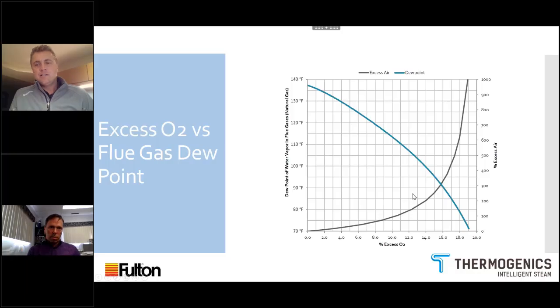So the number of hospitals we've been into, in particular brand new ones, that are designed around 130 degree F supply and 100 degree return, as you can see by this chart, if they're running anywhere above these O2 rates, you're not going to actually see condensing of that flue until you get down around 90 degrees. So it's important to understand the style of the appliance that you might be wanting to retrofit into an application and its performance on condensing, because we have had some very sad energy advisors standing by a boiler returning 100 degree Fahrenheit return temp with zero condensate coming out of it.